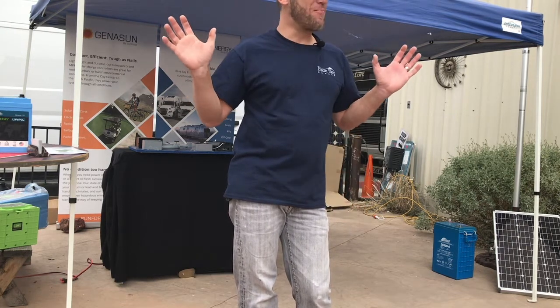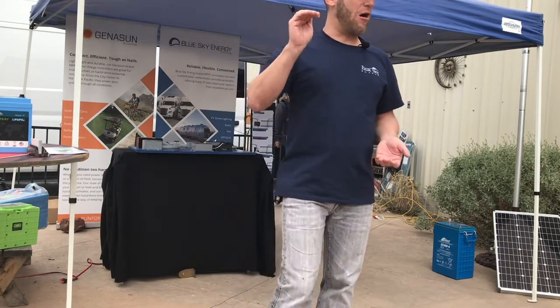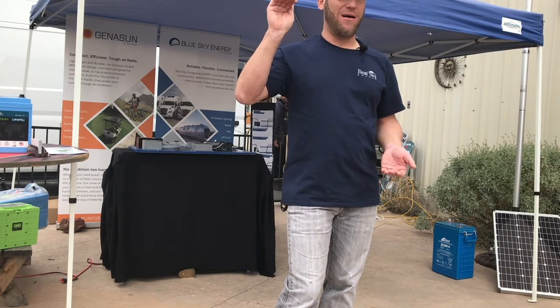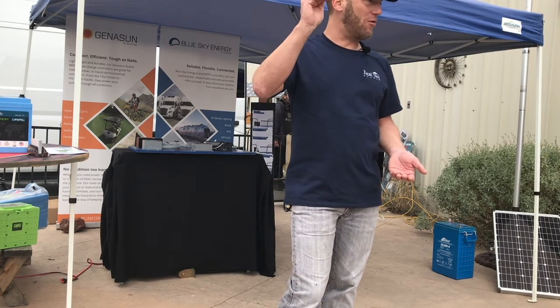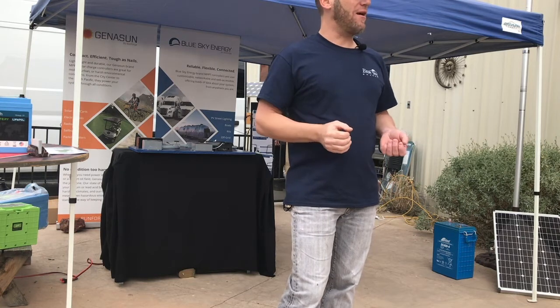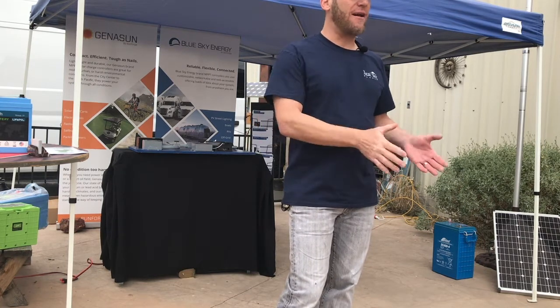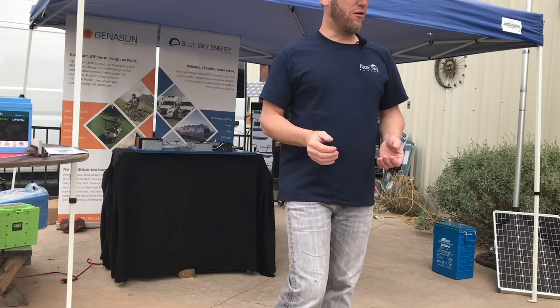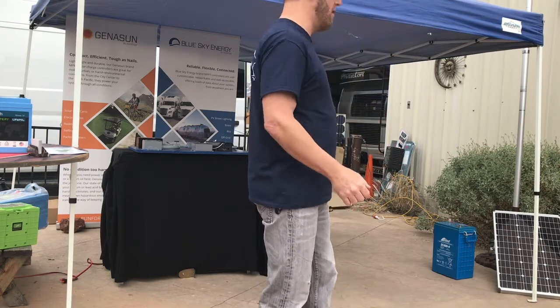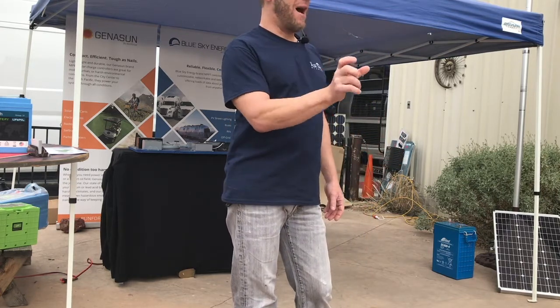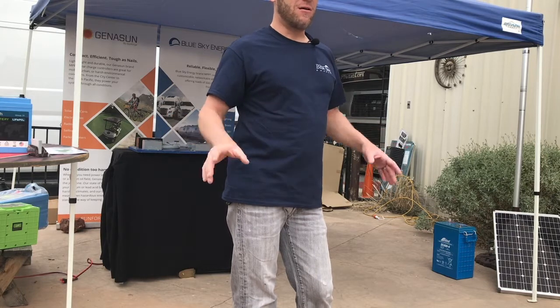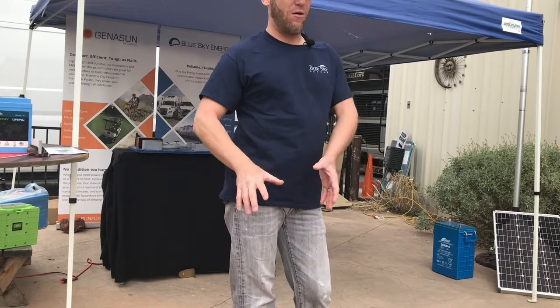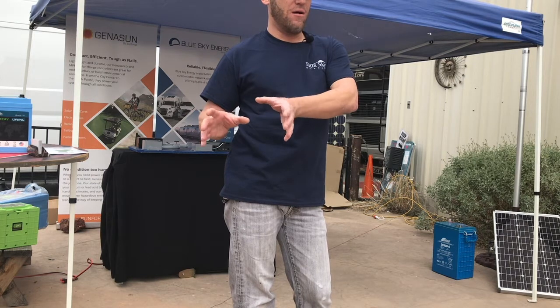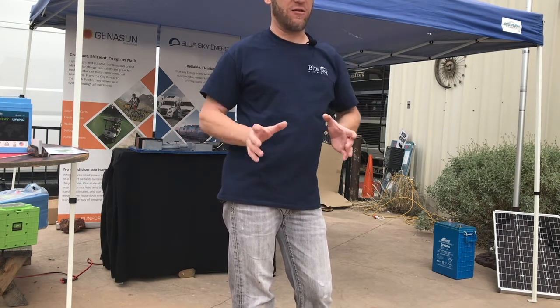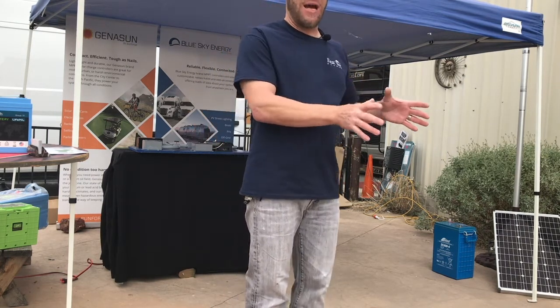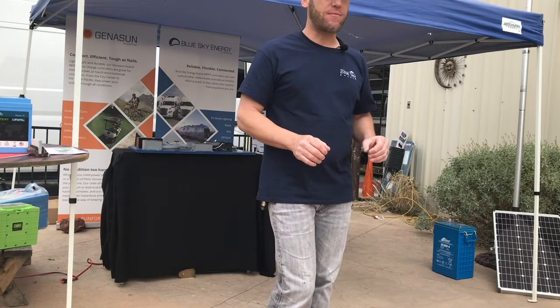And that's okay, but at some point that amount of power becomes redundant - you're just wasting your time because you're just providing power to keep it at that higher voltage. So the other way to make that transition happen is to base it on the net current reaching the battery. In order to do that, you install a current shunt, and I have one up here. You install a current shunt between your battery bank and everything else, so between all loads, charge sources, your ground, that all connects to one side of the shunt. We term it the load side, but that's just a term. And then just your batteries are connected to the battery side of the shunt.